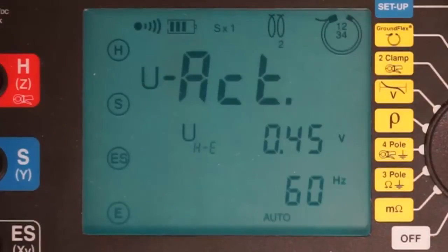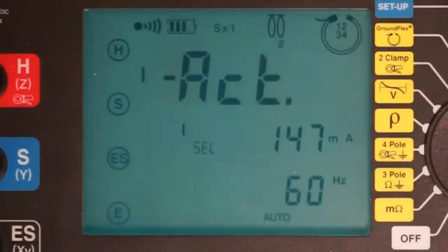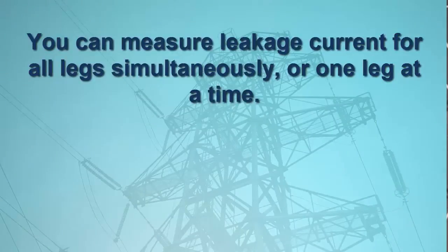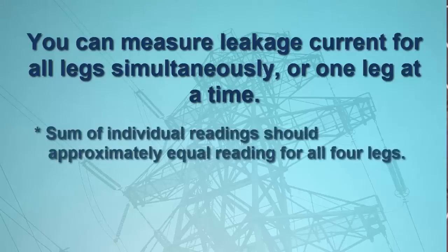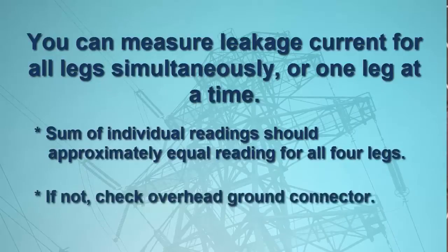Another press of the display button shows the leakage current flowing through the tower to the ground. In our example, which is measuring the leakage current for all 4 tower legs, this is around 150 milliamps. You can also measure the leakage current for each tower leg individually by turning the input dial on the Model 6474. The sum of the individual leakage currents for the legs should approximately equal the leakage current measured for all 4 legs simultaneously. If this is not the case, for example, if the measurement of the combined legs is near 0, while the sum of the individual legs is significantly higher, the overhead ground conductor may be disconnected from the tower, perhaps due to corrosion, and should be inspected.